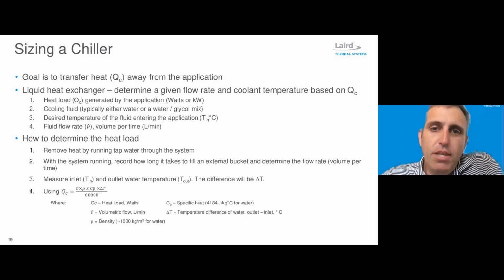And so we can get by with a pretty simple experiment in order to find out some of this information. We can use tap water to determine what these requirements are. So with the instrument installed and operational, we can run tap water through the system. In this experiment, we know our fluid is water. While the water is running, we can fill a bucket. Knowing the volume of the bucket, we can time how long it takes to fill it. This gives us a volume per time, which can be our flow rate.